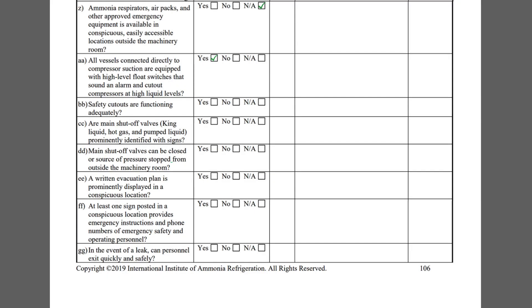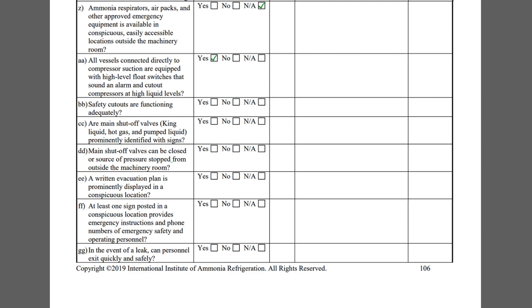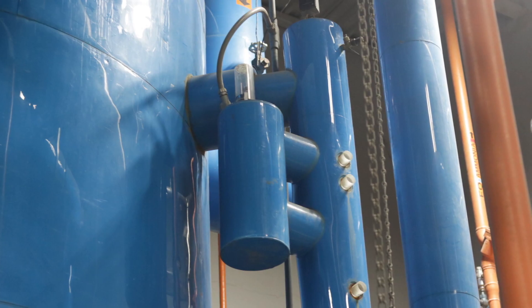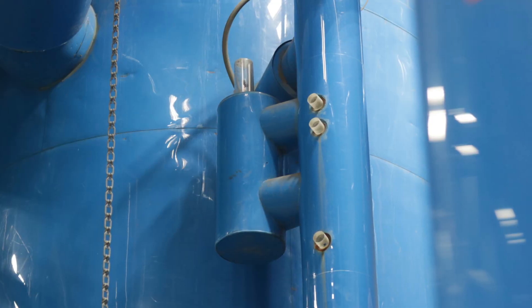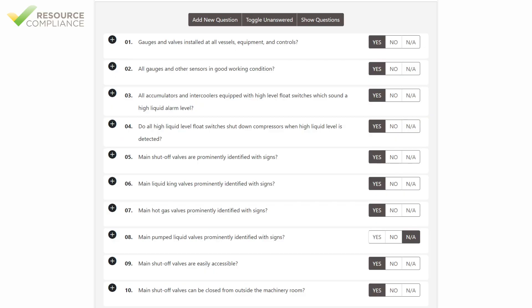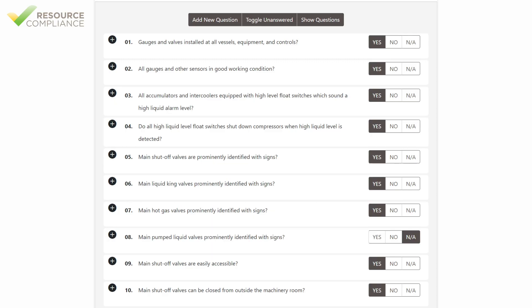Item AA asks if all vessels connected directly to compressor suction are equipped with high-level float switches that sound an alarm and cut out compressors at high liquid levels. This high-temperature recirculator has a high-level float switch that was successfully tested. Item BB is a general inquiry about the functionality of all safety system cutouts. The inspector will likely need to review safety test documentation to answer this question.